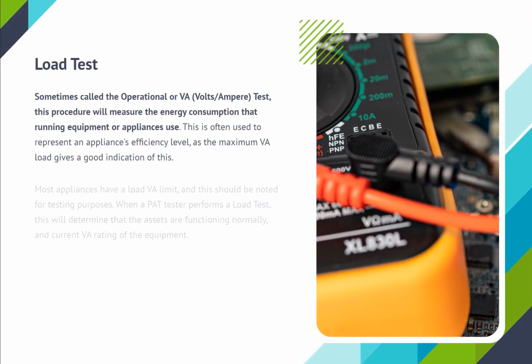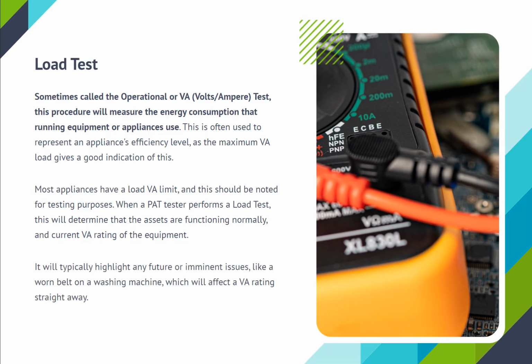Load test. Sometimes called the operational or volts or ampere test, this procedure will measure the energy consumption that running equipment or appliances use. This is often used to represent an appliance's efficiency level, as the maximum volts or ampere load gives a good indication of this. Most appliances have a load volts or ampere limit, and this should be noted for testing purposes. When a PAT tester performs a load test, this will determine that the assets are functioning normally, and the current volts or ampere rating of the equipment. It will typically highlight any future or imminent issues, like a worn belt on a washing machine, which will affect a volts or ampere rating straight away.